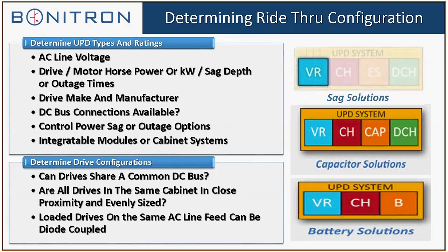And as we know by now, Bonitron is the DC bus guys, so we need to know if there are DC bus connections available. Some drives don't have the bus connections, but they do have kits that you can get that will give you pickoffs from the DC bus. We connect right across the bus capacitors on the DC bus, and you'll see that as we go along.